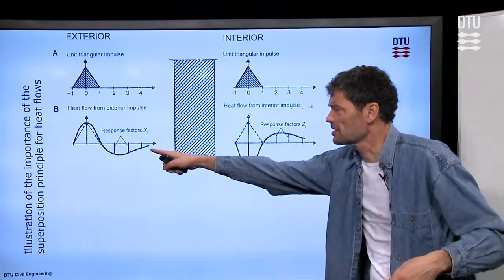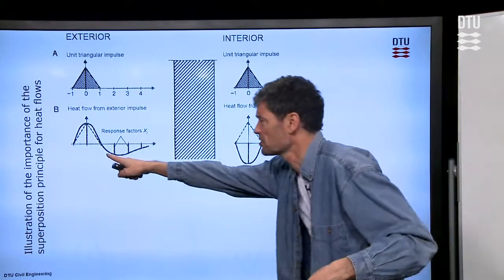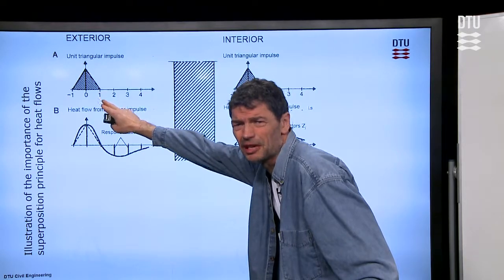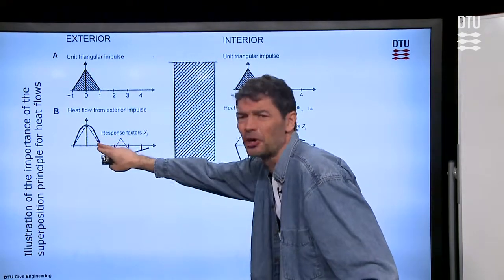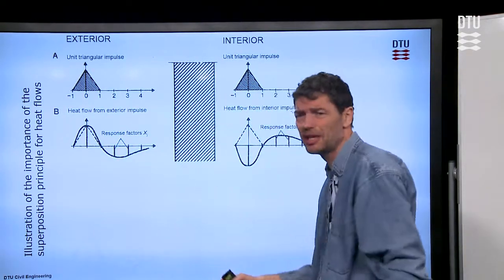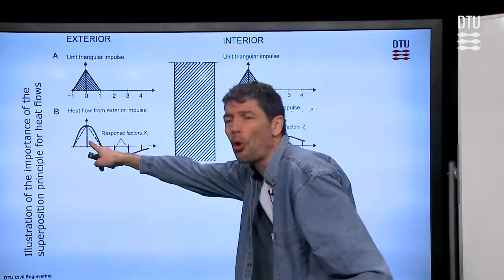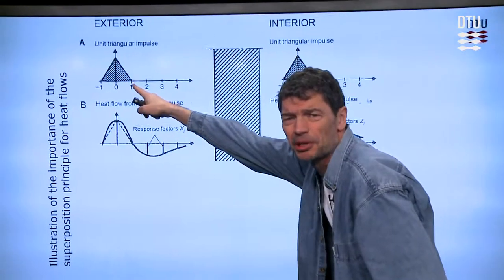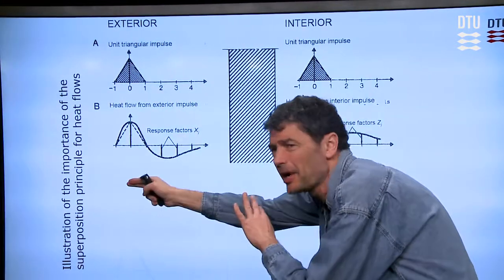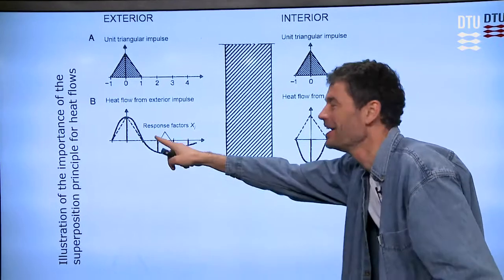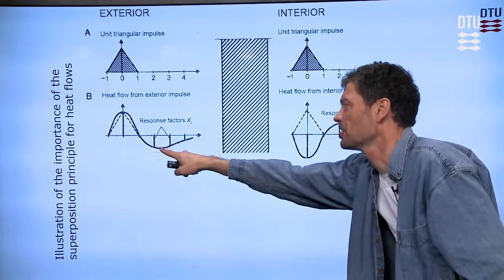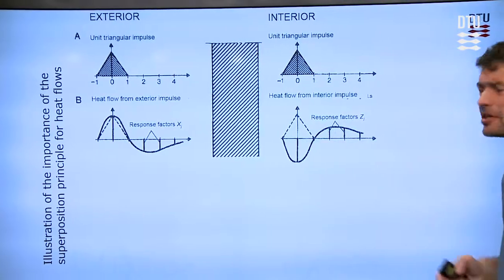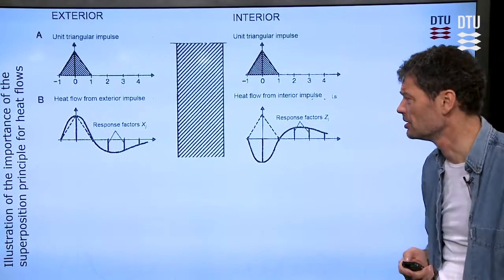Also, we see these response factors, they are themselves time dependent functions. So it tells us as a result of the temperature impulse on the left, first, we have heat flow going into the wall, which is in a positive X direction. So we have a positive X factor in the beginning. After a while, when the temperature impulse stops, well, then the heat is flowing back to where it came from, so to speak. And then we have a time sequence with smaller, but negative response factors. And we see the same on the right hand side with the opposite sign in front of it.